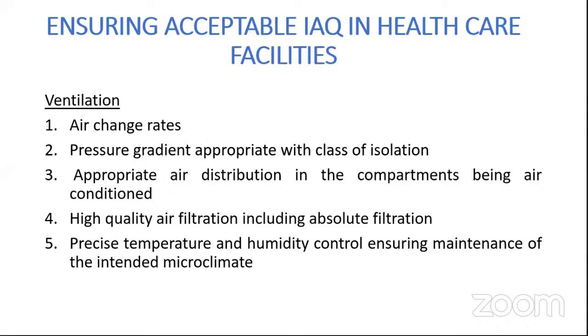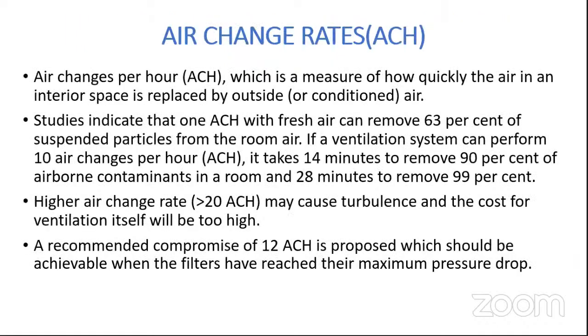When we look at healthcare facilities, that's a neglected area. We only talk about air exchange rates. We talk about pressure gradients. We talk about air distribution, filtration. But I think in the time to come, it is very important to understand that the CO2 levels in healthcare facilities will play a long-term role when we talk about a good ventilation system.